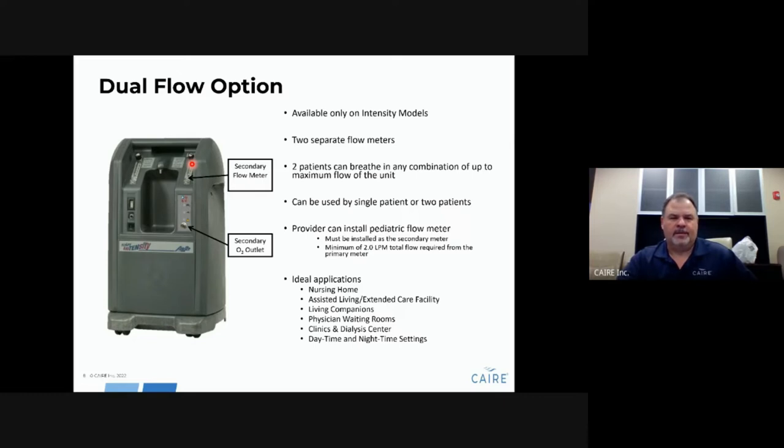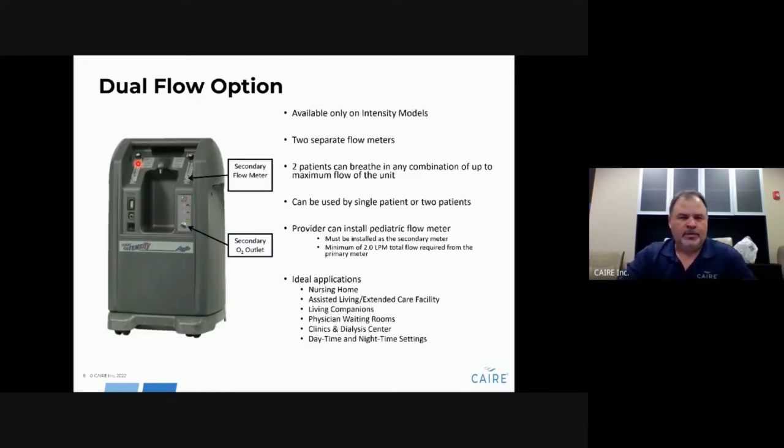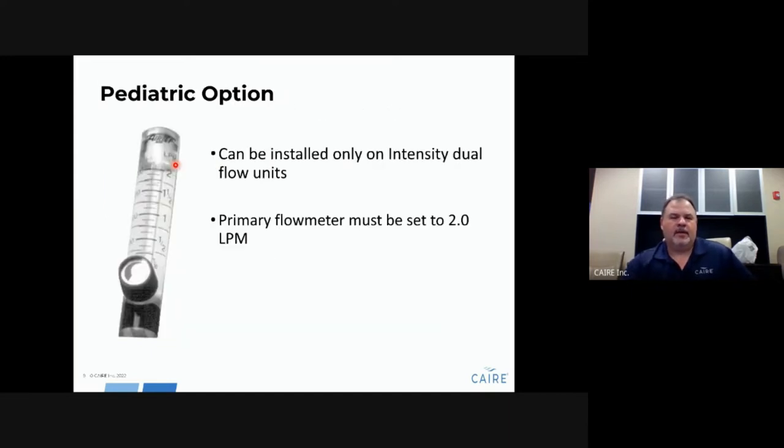This is the only unit CAIRE offers with a pediatric option. You can order a secondary pediatric flow meter separately. Once you receive the unit, remove the secondary flow meter, install the pediatric flow meter in its place. When the pediatric flow meter is installed and functioning, you are required to allow 2 liters per minute to bleed off from the primary flow meter. The unit requires a minimum flow of 2 liters per minute — if you turn it below 2, pressure will back up inside the unit, causing issues and alarms.